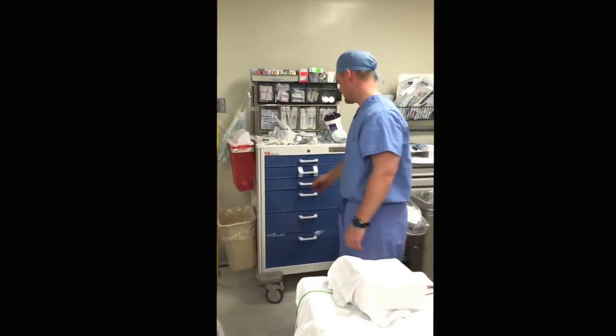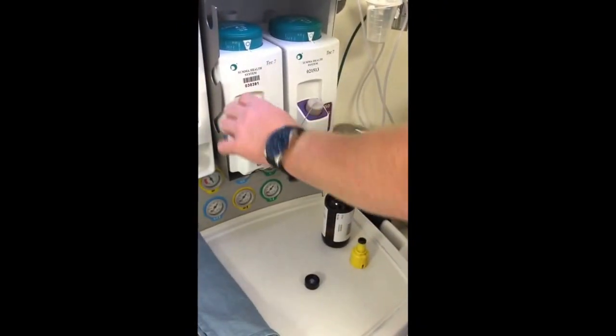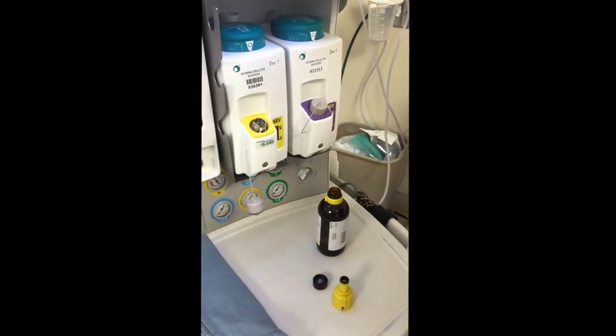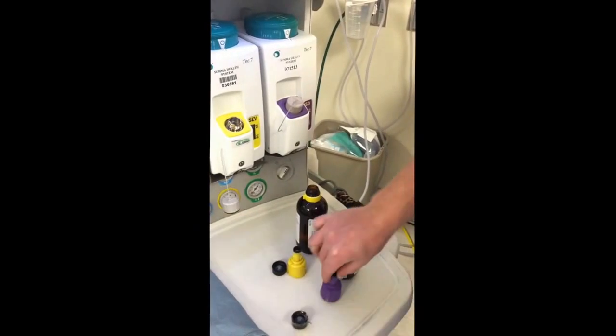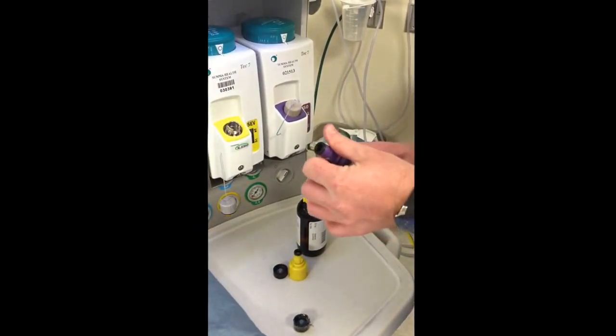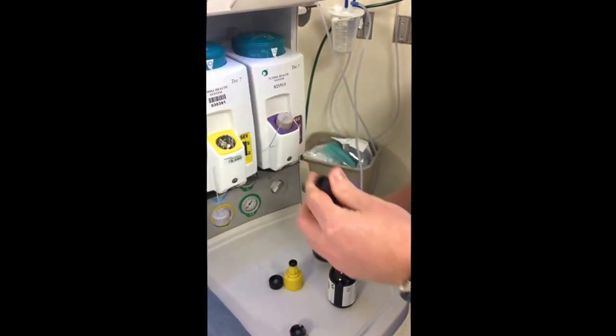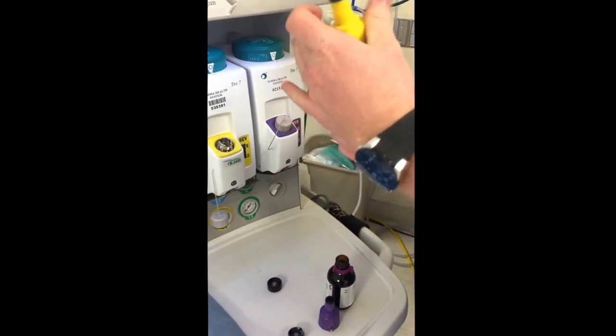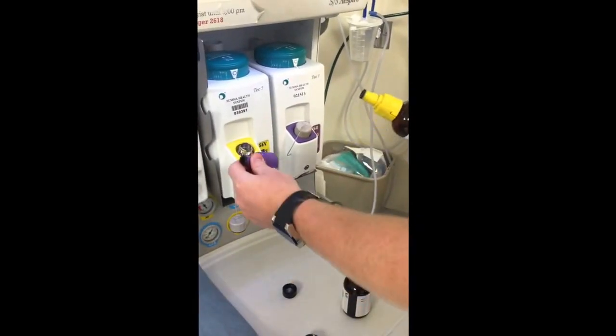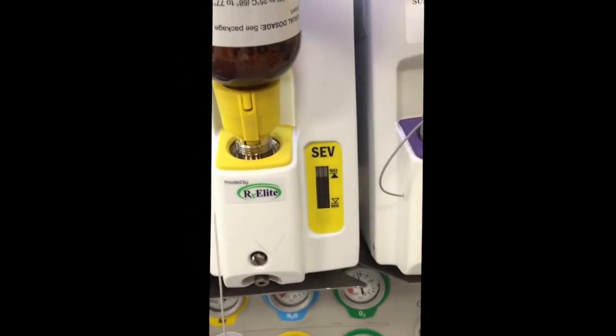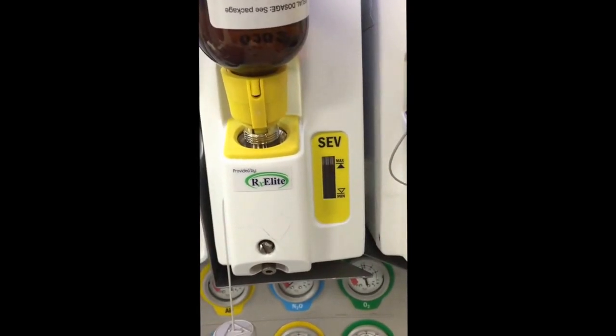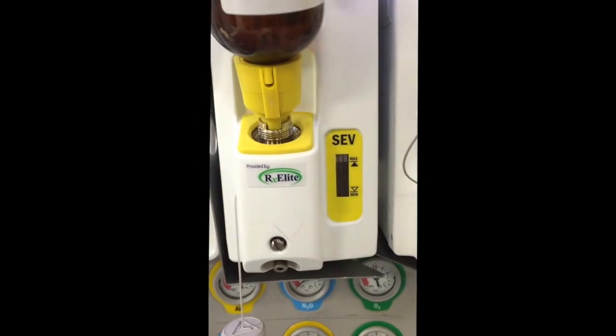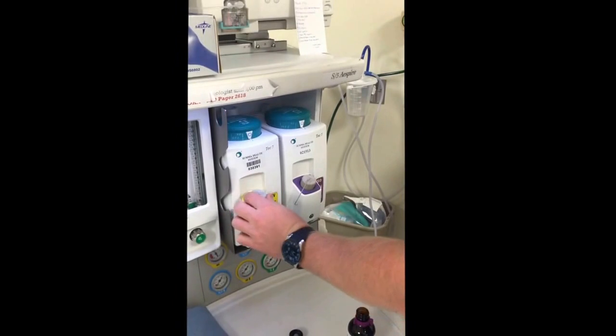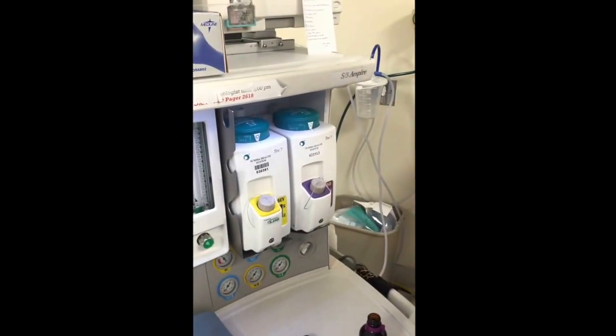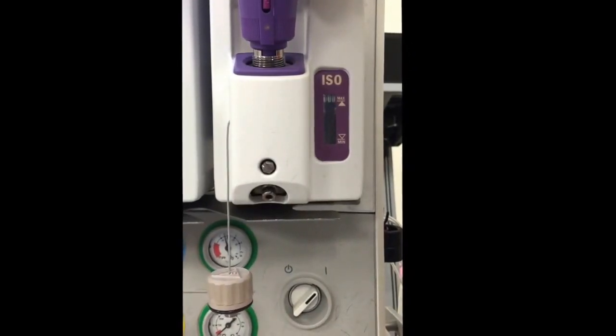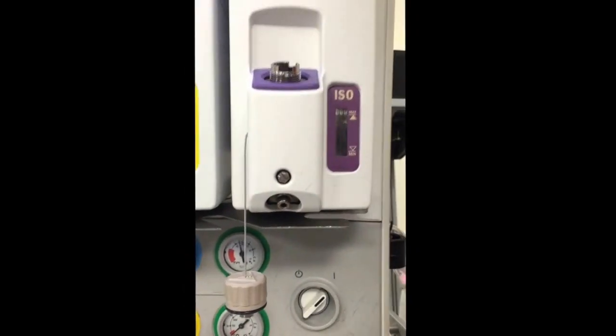What I like to do is fill my vaporizers at this point. So as you can see, your vaporizers come with color-coded fillers as a safety mechanism. The purple, which is ISO, won't fit on Sevo. So you match the colors, same thing, color-coded. This would not fit onto the Sevo. You press down to fill, and you can see the line filling. After it reaches maximum, it won't fill anymore. So that one's filled. Make sure your cap is tight. Once again, make sure your caps are tight.